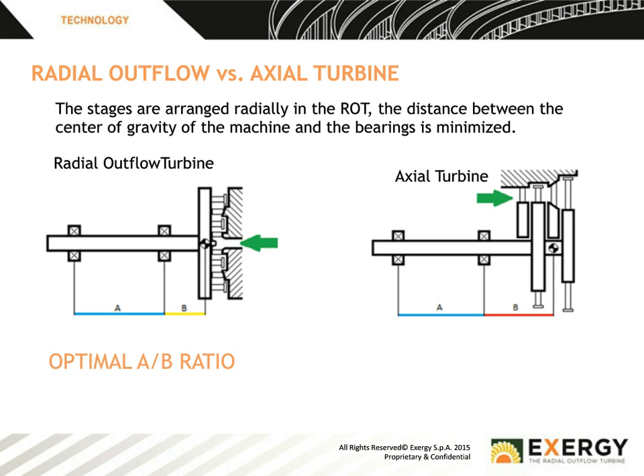If you go to a two-stage axial turbine, you have potentially higher vibrations. If you go to a three-stage, you have to move that center of gravity yet further from the bearings, which means you have again higher vibrations. And generally speaking, three-stage is the maximum you'll have on an axial overhung unit before the vibrations become too significant.